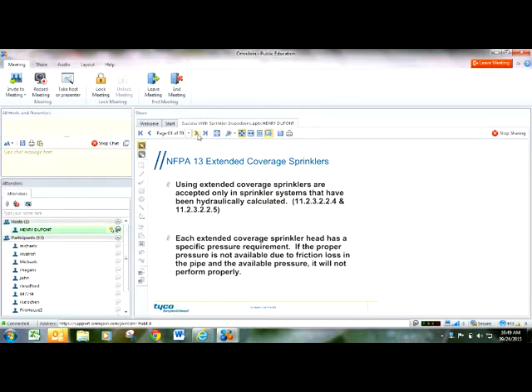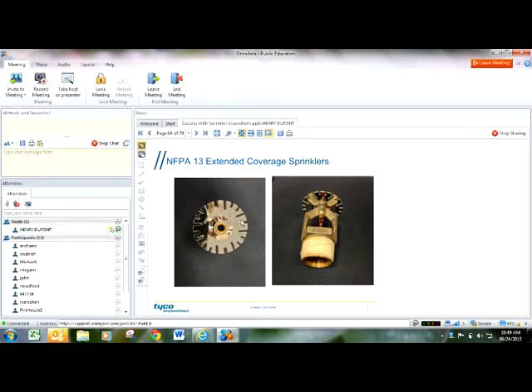You might ask, how do you tell what an extended coverage sprinkler head is? There's going to be something noticeably different about it compared to a standard sprinkler head. You can tell because of the big shape, the size of the deflector. Your standard sprinkler head has just a small deflector. Sometimes on an extended coverage sprinkler head, you have something sticking out, and I forget the exact term for it, but something protrudes out of the end of it. There's something you can look at and say, that's not a normal sprinkler head. Generally, that's telling you it's an extended coverage sprinkler head.